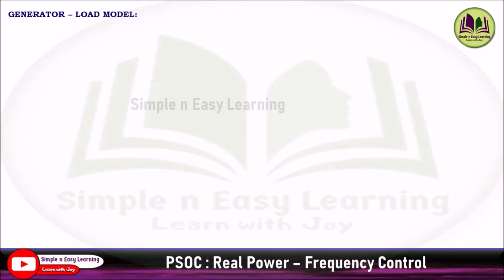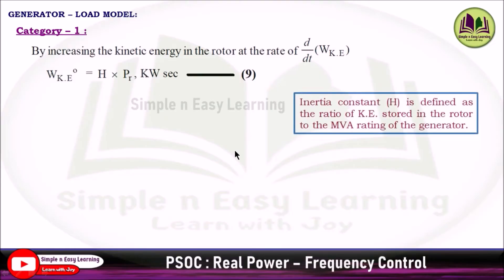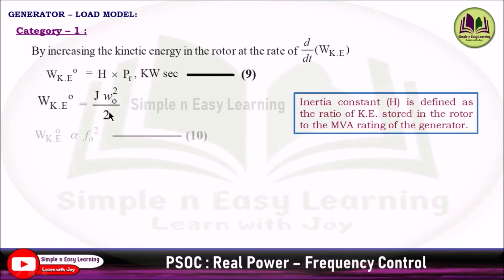Category 1: increasing the kinetic energy in the rotor at the rate d/dt(Wke). The initial kinetic energy is Wke₀ = H × Pr kilowatt-seconds (Equation 9), where H is the inertia constant — defined as the ratio of kinetic energy stored in the rotor to the MVA rating of the generator. The kinetic energy is given as ½·J·ω₀², where J is the moment of inertia and ω₀ is the angular velocity.